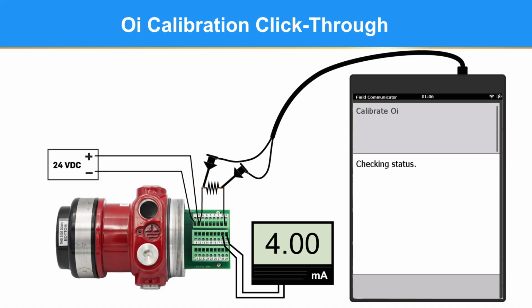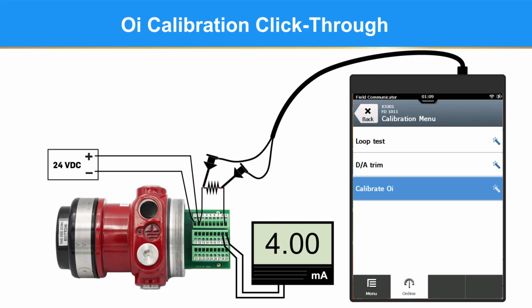The detector will now go through its OI calibration program. The time it takes to complete the calibration depends on how far off the OI values were before you started, so be patient. You will eventually get instructions to remove the cover when the procedure is complete. Select OK, and then all done. The OI calibration procedure is now complete.